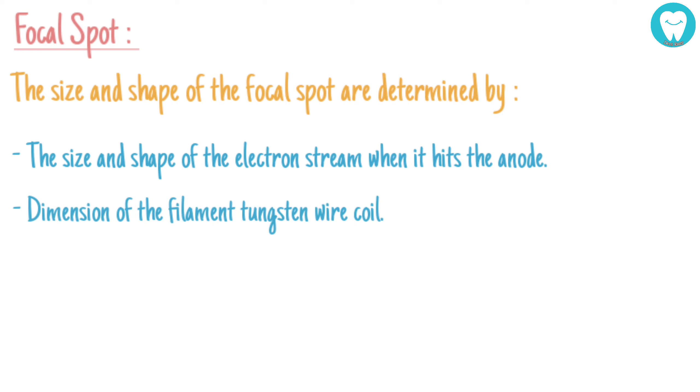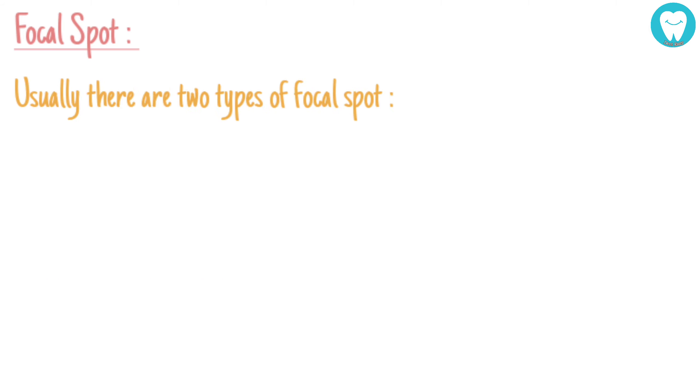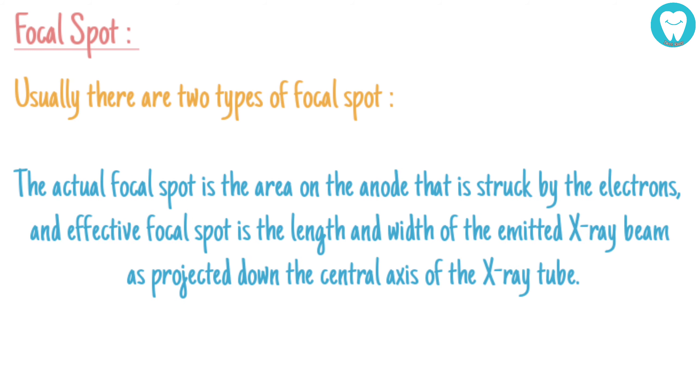Dimension of the filament tungsten wire coil, construction of the focusing cup, and the position of the filament in focusing cup. Usually there are two types of focal spot: the actual focal spot is the area on the anode that is struck by the electrons, and effective focal spot is the length and width of the emitted X-ray beam as projected down the central axis of the X-ray tube.